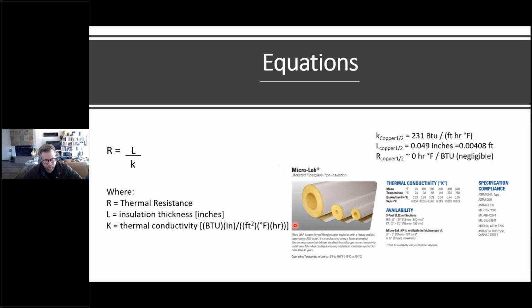And so when you look at this example of an insulation manufacturer, you can see that based off of the chart here and the fluid temperature, you can make an assumption and probably interpolate a BTU, a thermal conductivity, probably in the range of, assuming 140 degrees Fahrenheit, probably around 0.25, 0.26, somewhere in that range. And you would plug that into that equation based off your insulation thickness. And again, we're going to assume copper is in essence negligible when we're going through this. And again, I'm using copper as a base material.